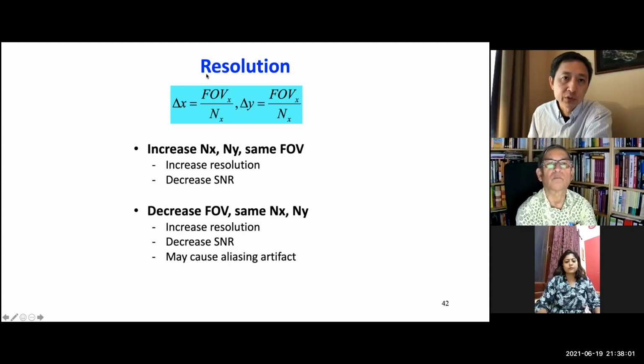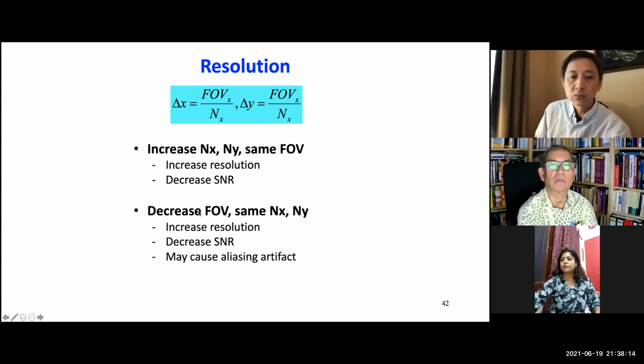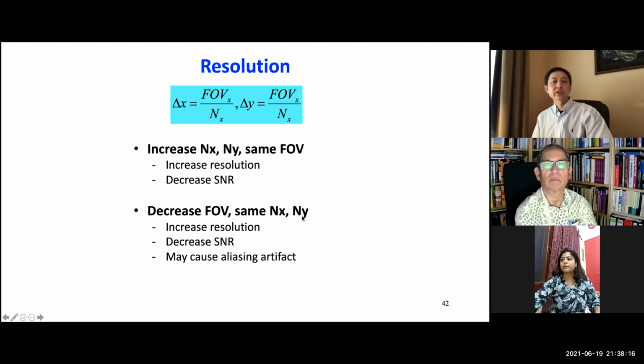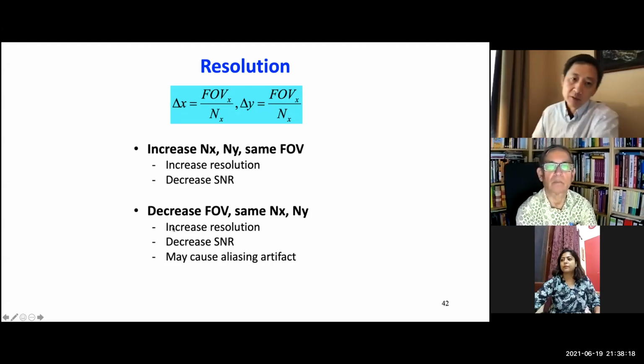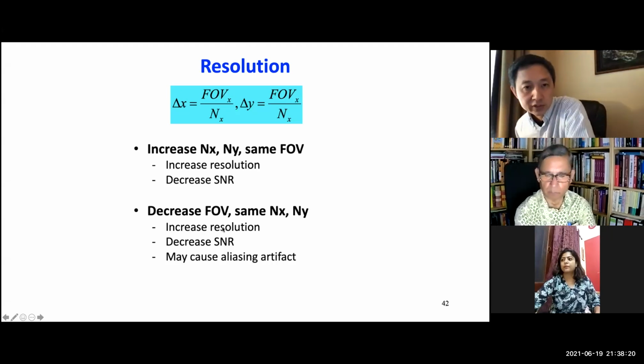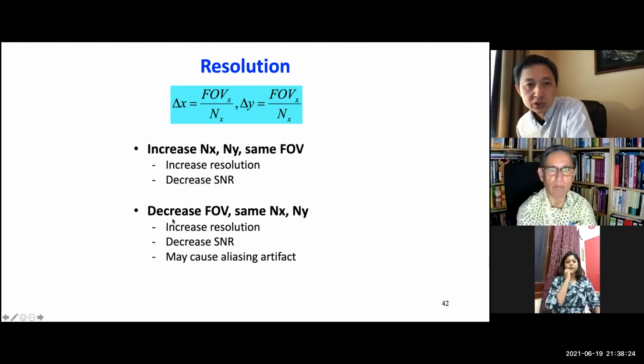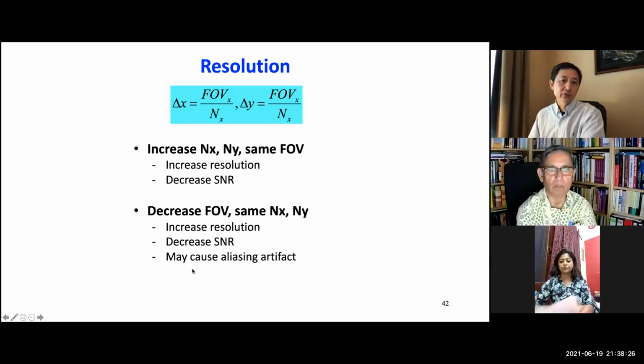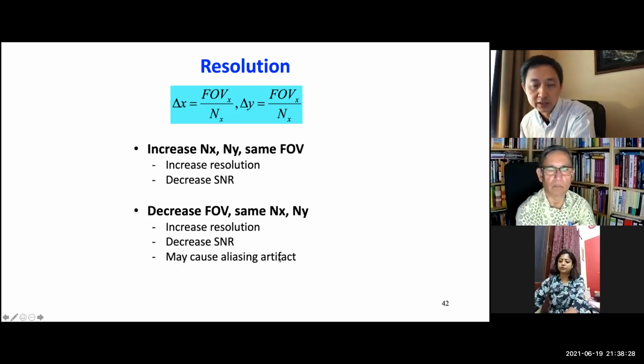Resolution is very simple. It's just FOV divided by matrix. When we increase the matrix size with the same FOV, we have better resolution, but that will decrease SNR. When we decrease FOV with the same matrix size, that will also make the pixel size smaller, better resolution, but that will decrease SNR. Also, when FOV is smaller, we can cause aliasing artifact.